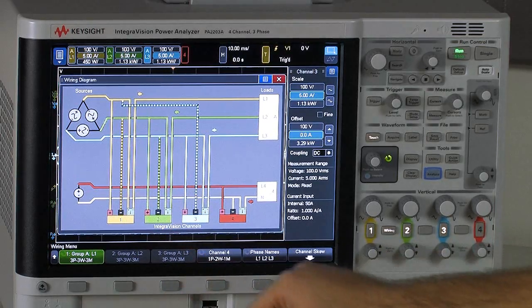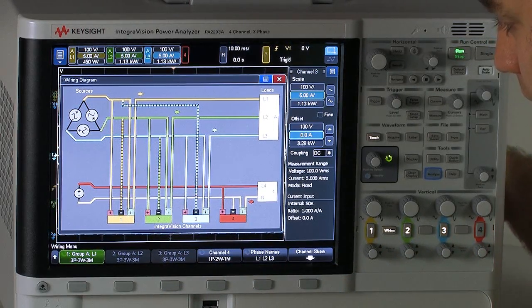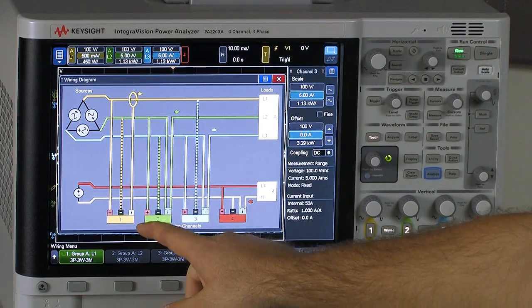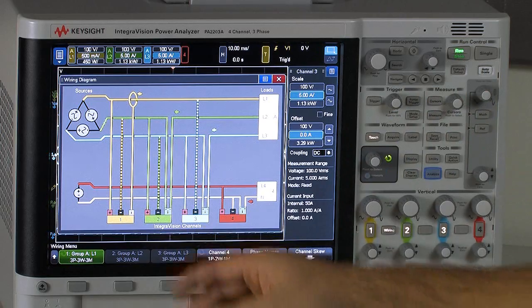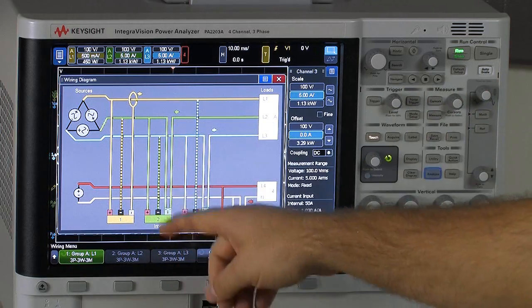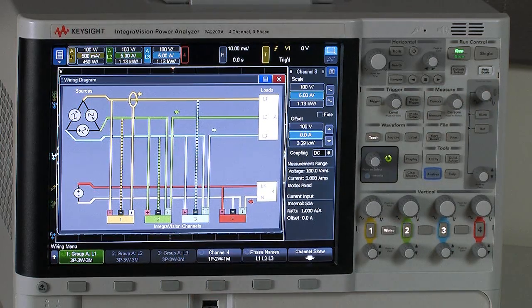And one thing we can see is if we actually change the state of the current input from the internal shunt path to the external transducer input, we can see the wiring diagram automatically updates to reflect that.